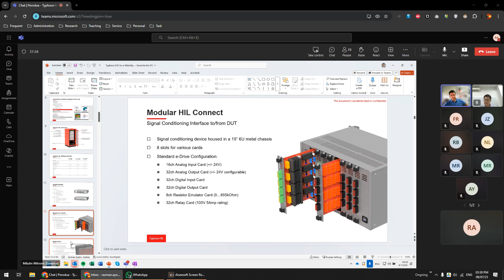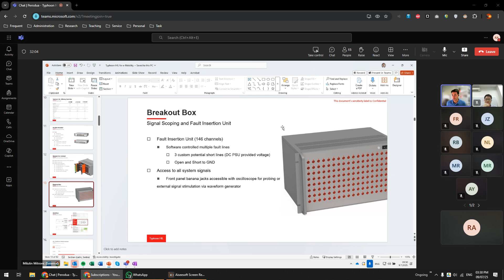When it comes to the breakout box, we have 146 channels, and they're software controlled. The whole fault insertion is software controlled, but it's actual physical fault insertion. The fault line is supplied to the breakout box, and you insert that fault potential into your circuitry. You also have access to all the system signals on the front panel, so you can physically attach an oscilloscope and check what's going on there.